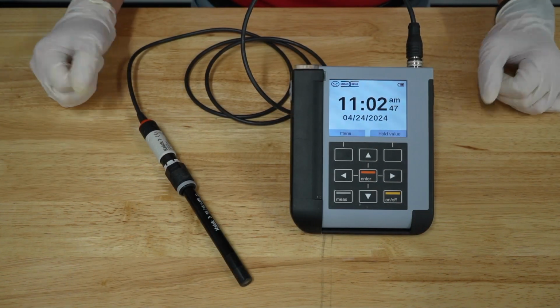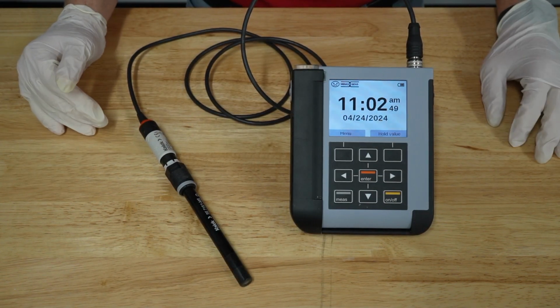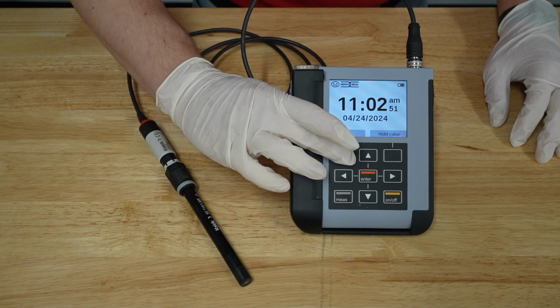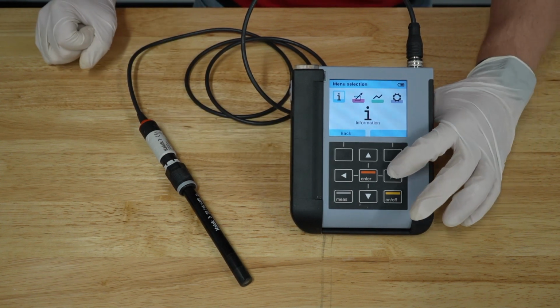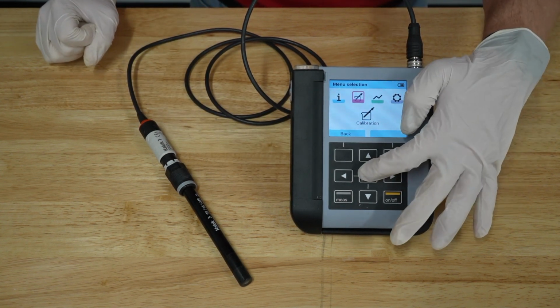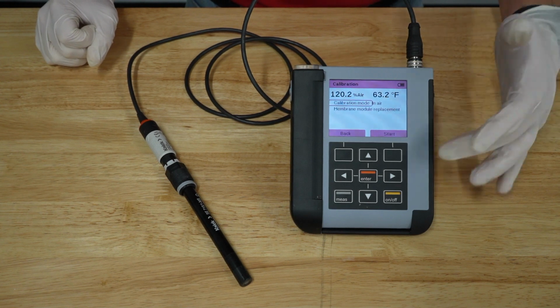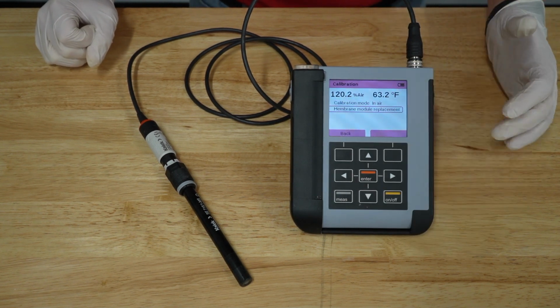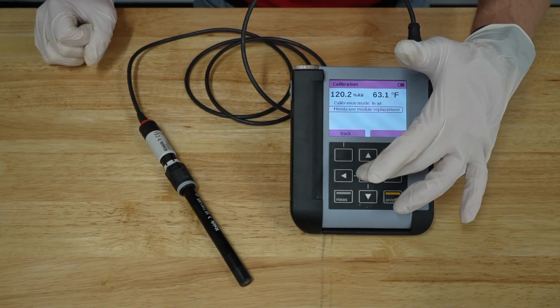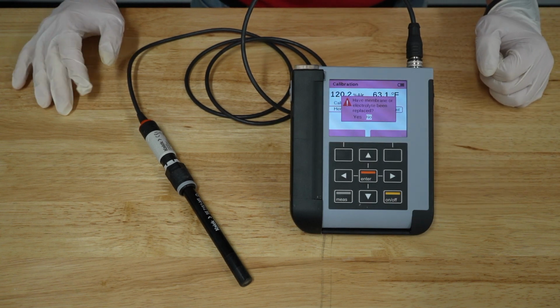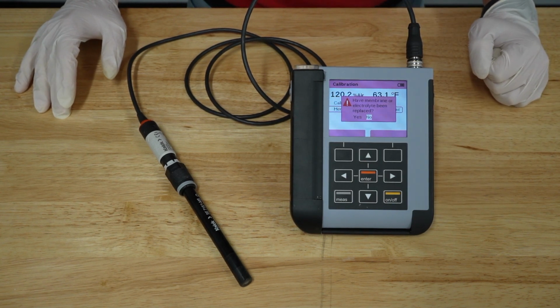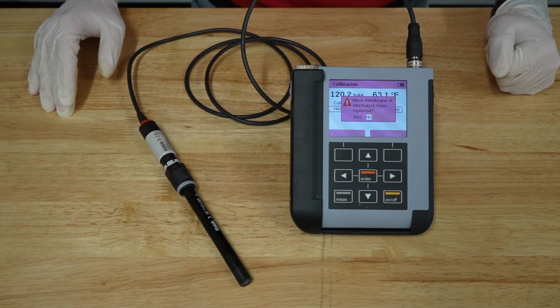The last step is to tell the sensor it's had the membrane replaced. We'll go into the menu on the Portavo, scroll to the calibration menu, and with this sensor connected, go to the membrane module replacement. Hit enter, and you'll be prompted with a screen asking if you've replaced the membrane.